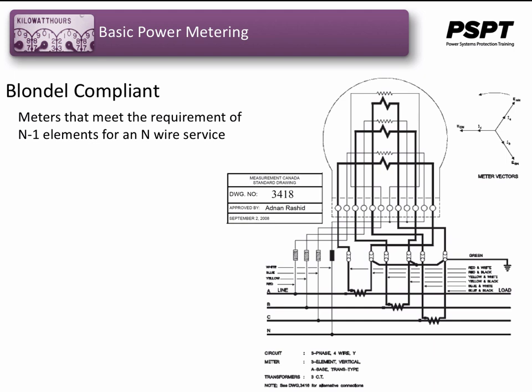We did an example of 100% Blondel compliant metering in our example of a 3-element meter using Measurement Canada's standard 3418, as seen here. You can see that there are 4 wires and we are using 3 elements, which meets the requirement of n-1 elements for n wires.